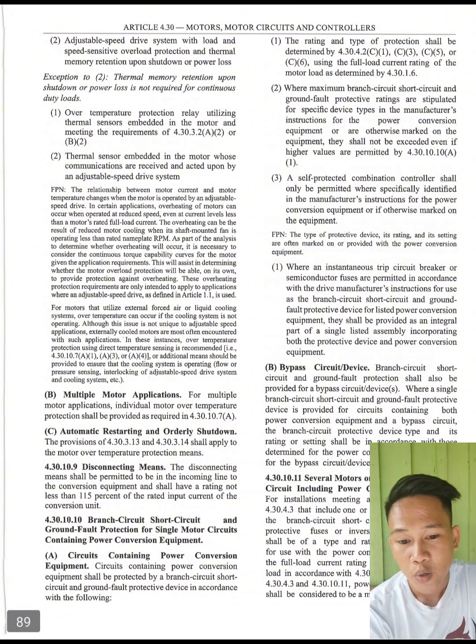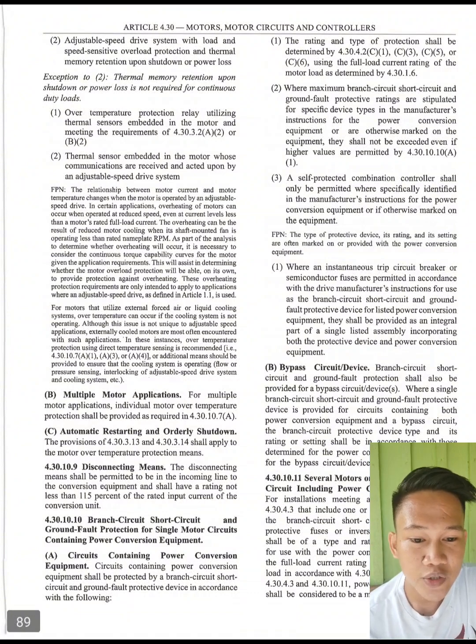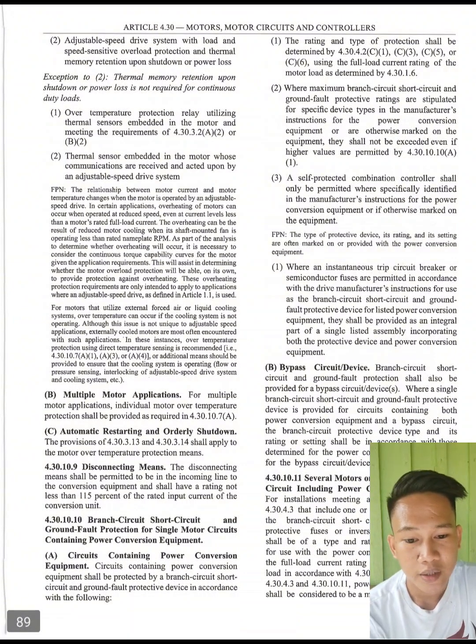So next we have 4.30.10.9 disconnecting means. The disconnecting means shall be permitted to be in the incoming line to the conversion equipment and shall have a rating not less than 115% of the rated input current of the conversion unit.